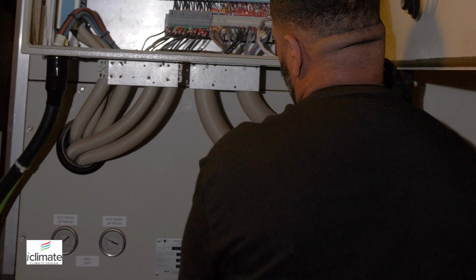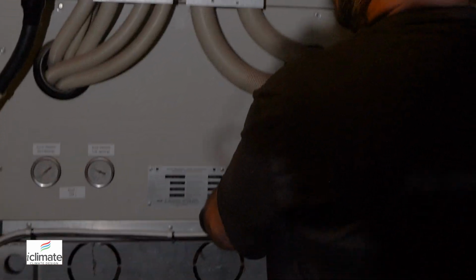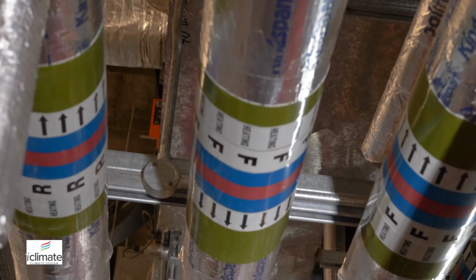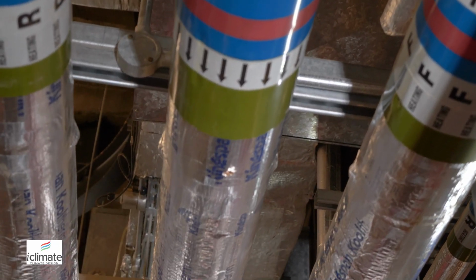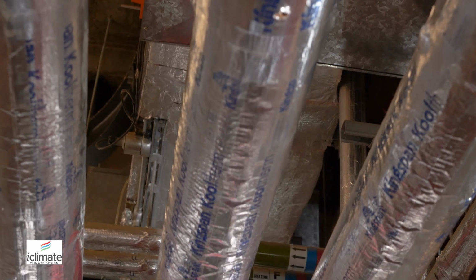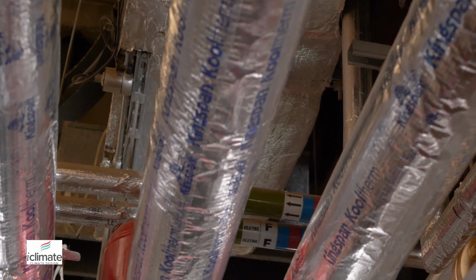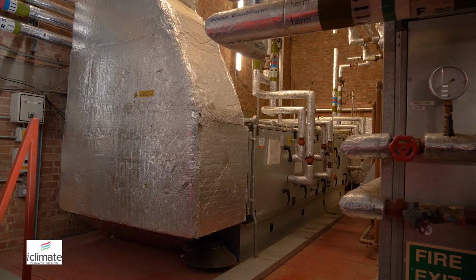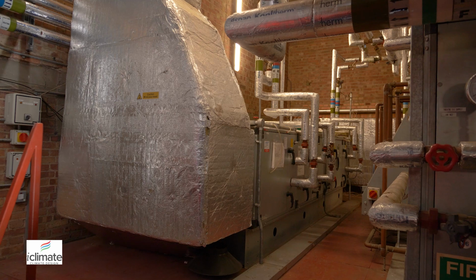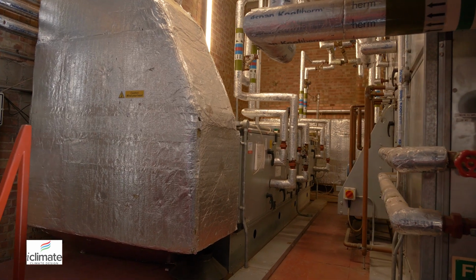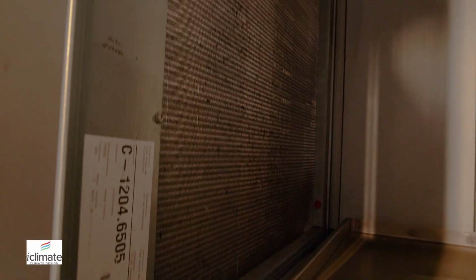This chiller is 142 kilowatts capacity at 35 degrees C condenser ambient, and it will provide a delta T of 7 to 12. That means that this chiller will pump 7 degrees C chilled water through the pumps to the local fan coil units, which are basically the water AC units within the building. Or in this scenario, it will provide it to the air handling units that are supplying all the air into the space, and it conditions it there. So the air handler is essentially a very, very large fan coil unit for the entire building.